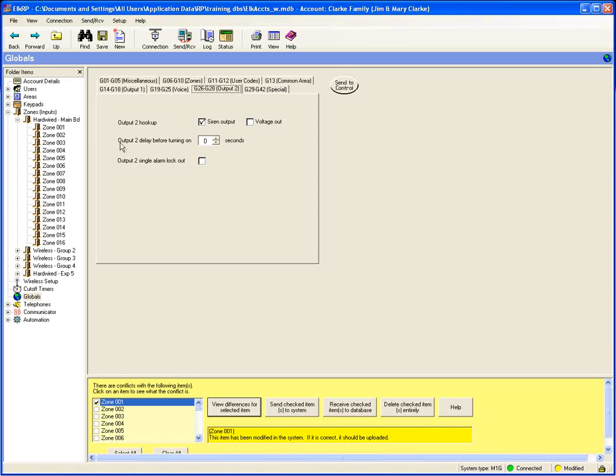You can also set a delay on Output 2 — typically that's the outside siren. If you want a delay before it goes off, that's a peacekeeper feature so you don't alert the neighbors if it's an accidental alarm. There's also a single alarm lockout, which means within one arm cycle, Output 2 is only going to go off one time. If there's another alarm, Output 1 would still go off but Output 2 would not if that's enabled.